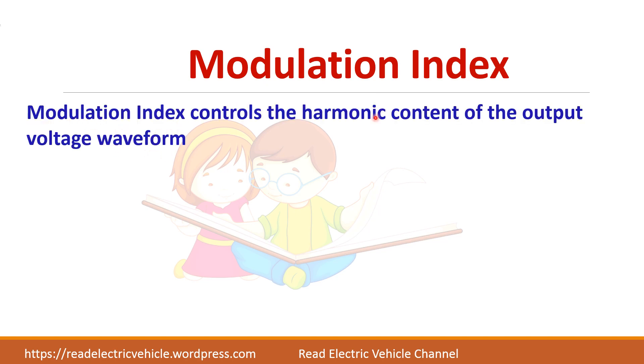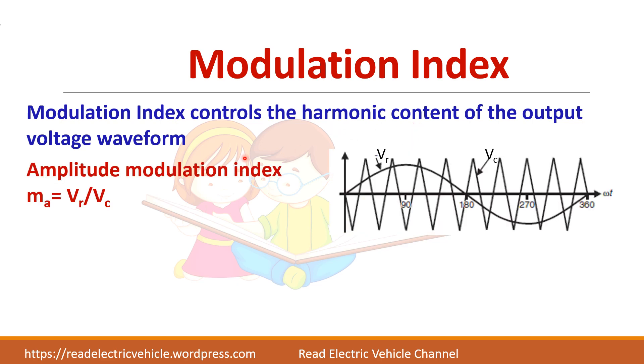Two important terms in SPWM are modulation index and frequency modulation ratio. The modulation index (ma) is the ratio of the reference wave amplitude VR to the carrier amplitude VC. This ratio controls both the harmonic content and the magnitude of the output voltage waveform. In normal operation, ma is always less than 1, meaning the sine wave magnitude is always less than the triangular waveform magnitude.